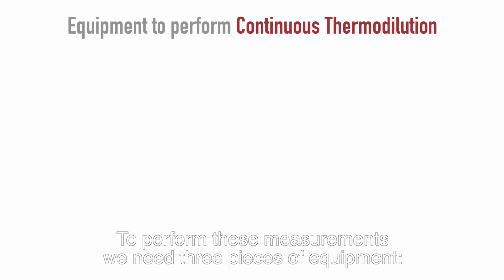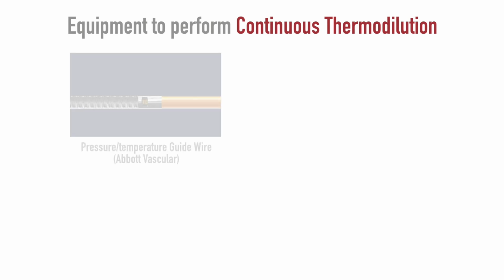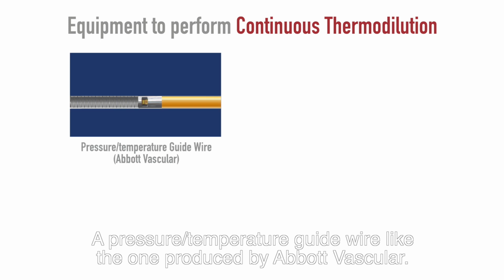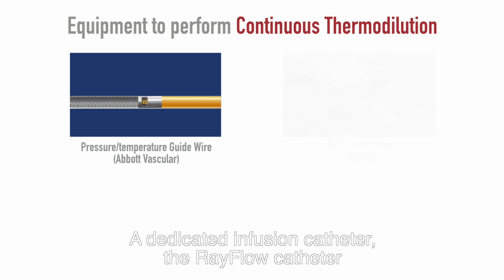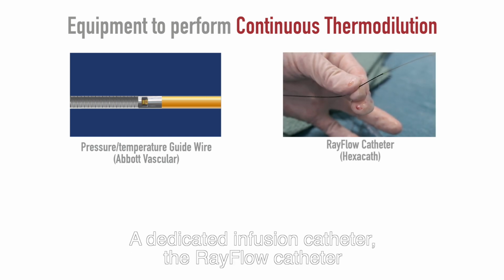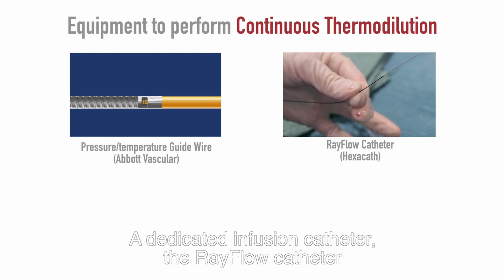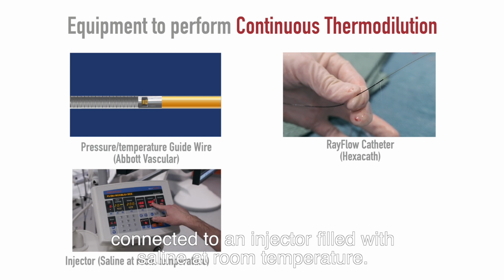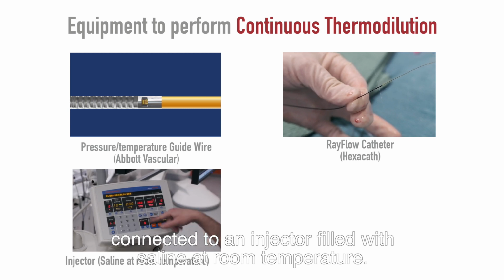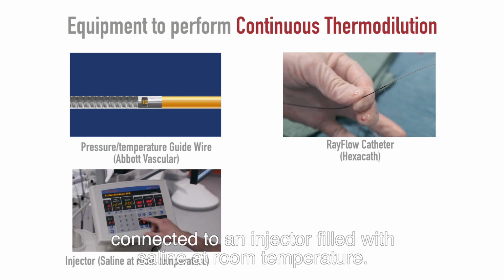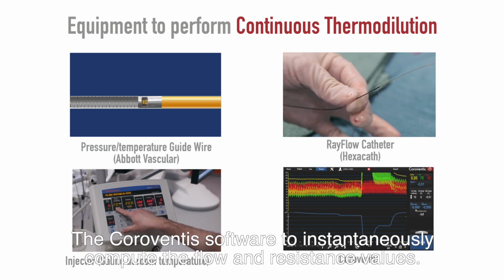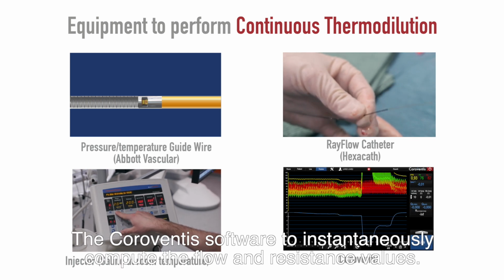To perform this continuous thermodilution, we need three pieces of equipment. A pressure/temperature guide wire as produced by Abbott. Second, we need a dedicated infusion catheter, which is called a RAYFLOW catheter produced by HEXACATH, which has to be connected to a pump filled with saline at room temperature. And we need a software called Coroventis to calculate all these measurements online.